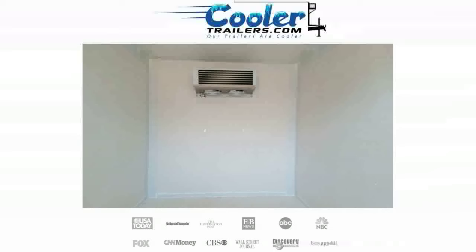In order to maintain a box temperature of 35 to 40 degrees Fahrenheit, plus opening and closing your doors, your evaporator coil has to be at least 10 to 12 degrees colder, or about 25 degrees, to maintain that 35 degree box temperature you're asking it to keep. So it's a scientific fact that you will get an ice buildup on your coil. It's just a matter of when.